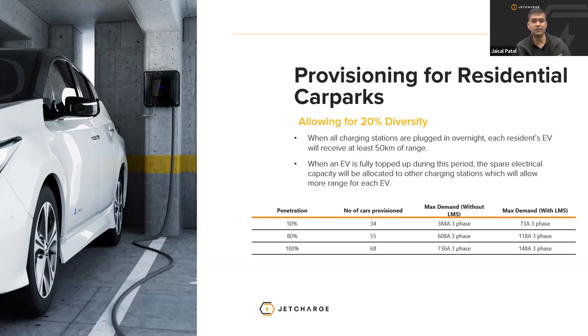At 80% penetration and 55 car bays, you require 608 amps three phase without load management, but with load management, you only require 118 amps, which is still within the boundaries of what we can integrate. And at 100% provisioning, 68 cars for the entire residential car park, 736 amps, which is again quite a lot, but with 148 amps three phase, we allow 50 kilometers of range for each resident with overnight charging at its worst case scenario. But what we have found is that overnight charging typically has way more available capacity than you might expect, as most residents are not using as much power and there's more available capacity for the EV chargers. Next slide.